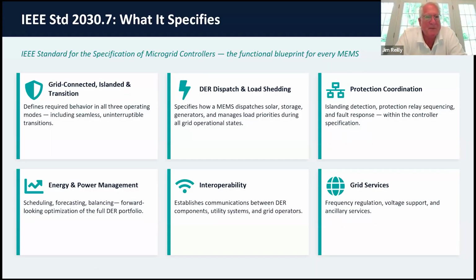These are the specifications of IEEE 2030.7. They're all things you want to look at if you have a grid-connected microgrid, especially at scale, that is going to be islanding. So obviously you're starting with behavior into operating modes, and mostly dispatch, transition, and reconnection are really the most important, because if you disconnect and you're not stable, you're not going to have anything. So then you're going into DER dispatch, load shedding, coordination with protection, which has become really important now.